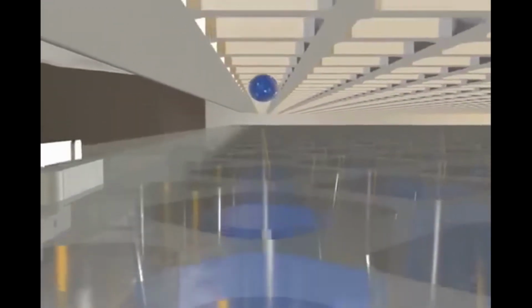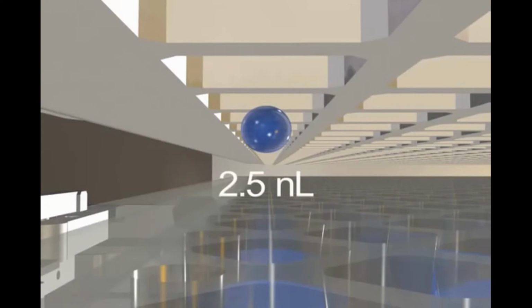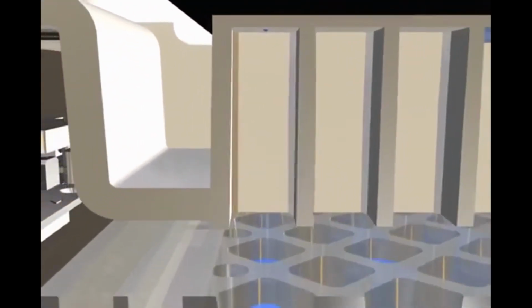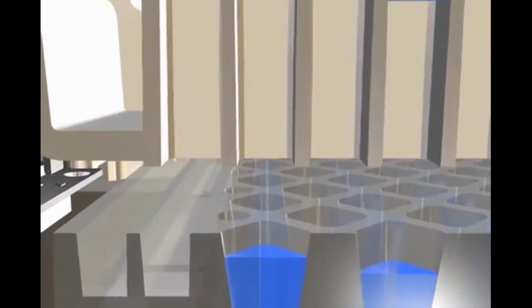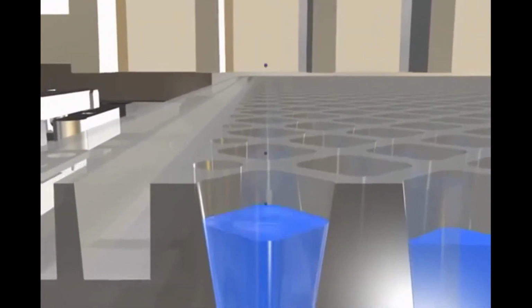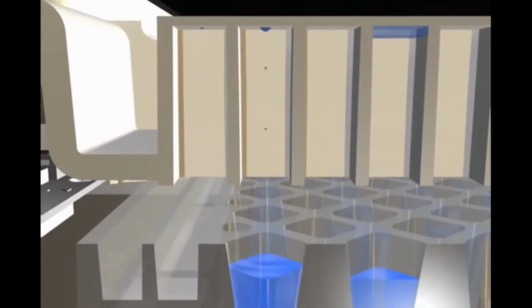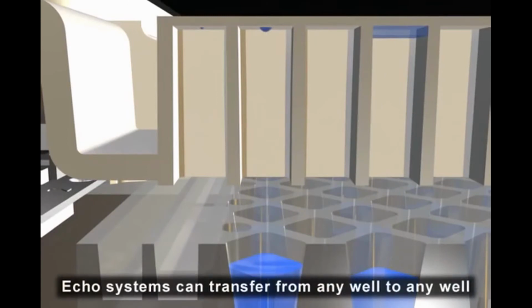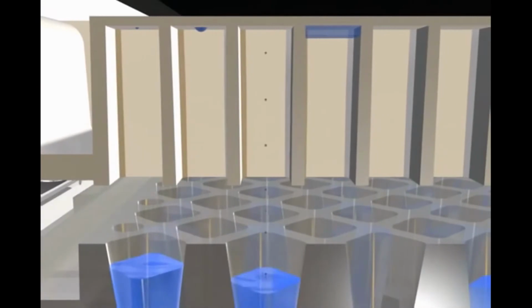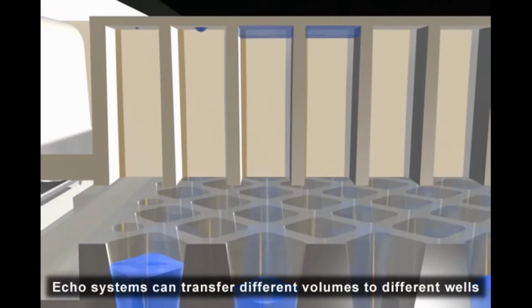The energy causes a 2.5 nanoliter droplet to eject from the surface and to fly up into the appropriate well of the destination plate above it. Surface tension captures and holds the droplet in the well. Fluid from the same source well can be ejected into another well of the destination plate. More droplets are ejected to increase the volume.